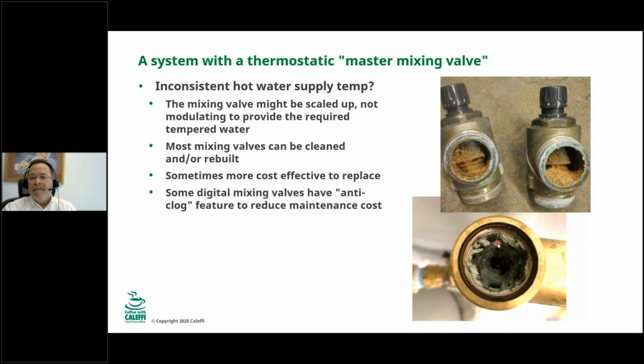And how often you have to do that really depends on a couple things. Number one, how hard your water is. The more minerals or deposits in your water, the more often you have to do it. How much water you use. If you have a family that uses showers a lot of hot water, the more water you put through it, the more minerals you're putting through it. And also how hot the water is. The hotter you run your domestic hot water in your tank, the more the minerals precipitate out of it. So if you're going to elevate your tank temperature to 140, like we've been talking about, expect to get more minerals.